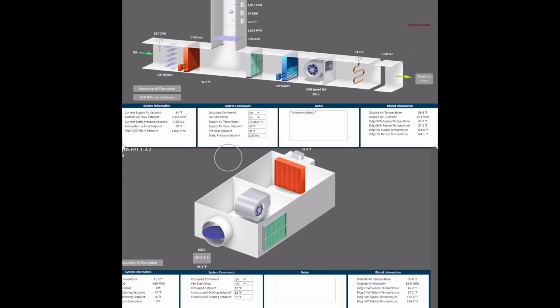the air handler unit with a little more specifics. On this side over here on the left, you are going to have your outside air. This is your outside air. You provide fresh air. On top, you're gonna have your return that comes from the rooms, from the area that you're cooling. That's your return air. Okay, now that we see the return air, we're gonna talk about the other specifics of the air handler.